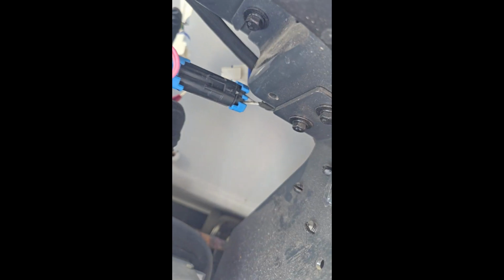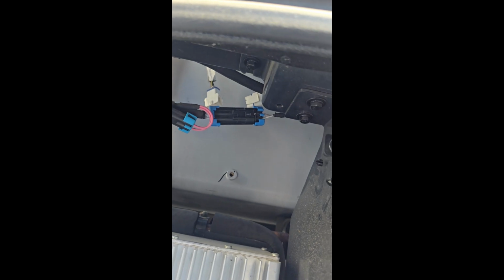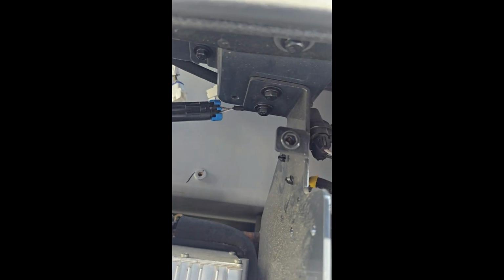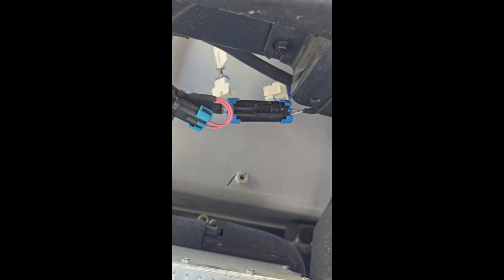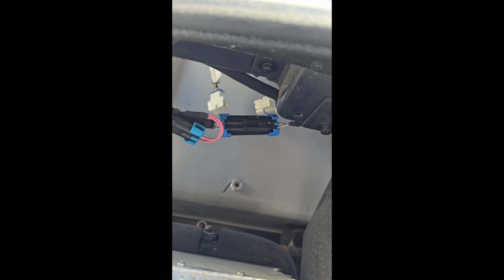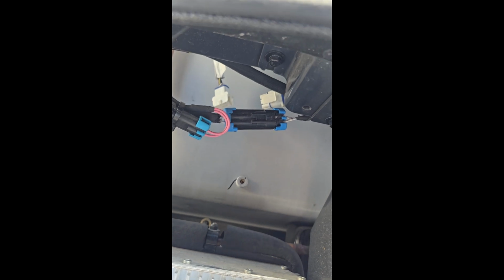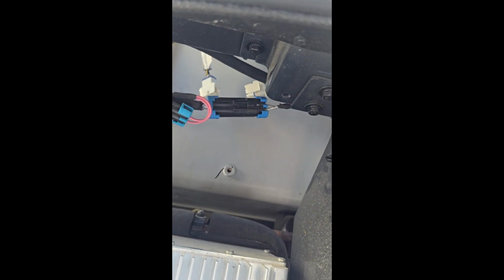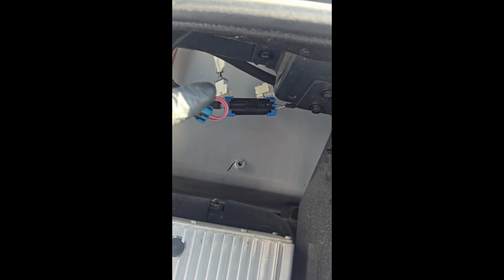So voltage has to come into this plug, it has to make continuity into the fan IP circuit, which has a positive thermal coefficient resistor in it, meaning the hotter it gets, the higher resistance it gets, and that makes the circuit literally look like open, but it's not. And then once it comes back down from the fan, it connects the circuit, which connects to our contactor.